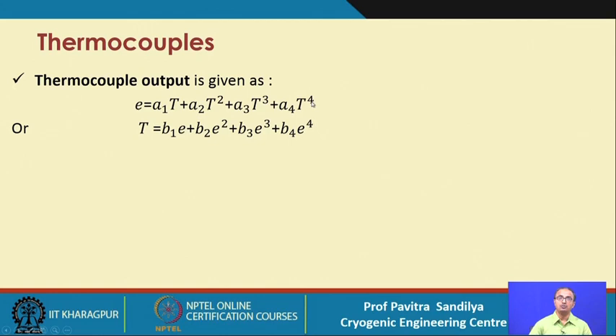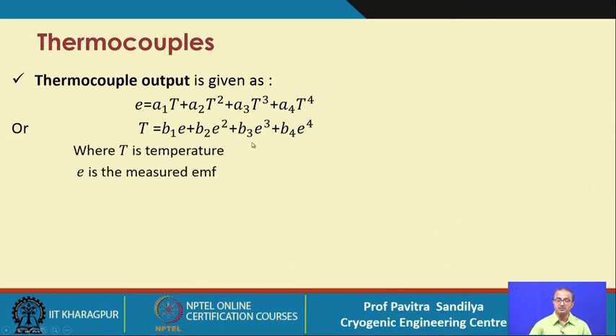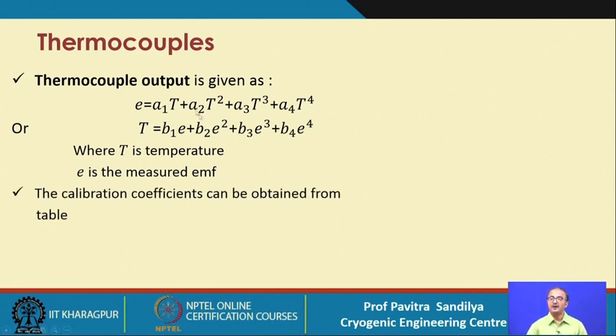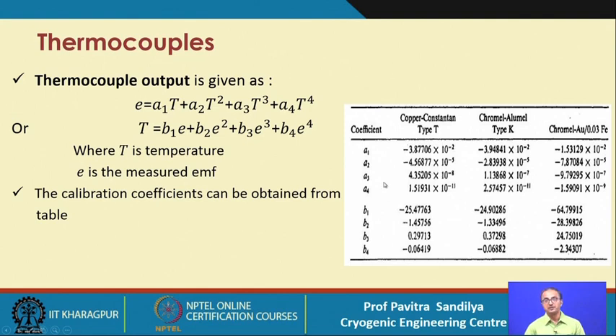There are various polynomial expressions to correlate EMF with temperature. The first expression shows how EMF depends on temperature and the second shows how temperature depends on EMF — both obtained empirically from experimental data using curve fitting or regression. The coefficients a and b can be obtained from standard tables; values are shown for copper-constantan (type T), chromel-alumel (type K), and chromel-gold thermocouple types.